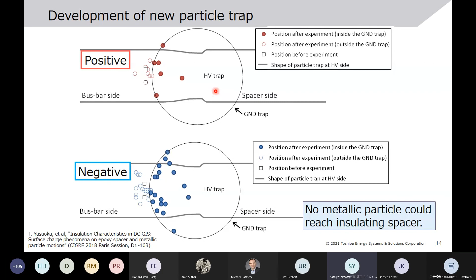And this figure shows the final location of the metallic particle after the DC positive and negative application. So the circle shows the shape of the grounded side trap, and also this shape shows the high voltage side trap. It means the conductor. So the location of the metallic particle is pointed on the picture. So you can see no metallic particle could reach the insulating spacer. The left side is the side where we put metallic particles, and the right side is the spacer side, and no particle could reach the insulating spacer beyond the traps. So it is quite useful.